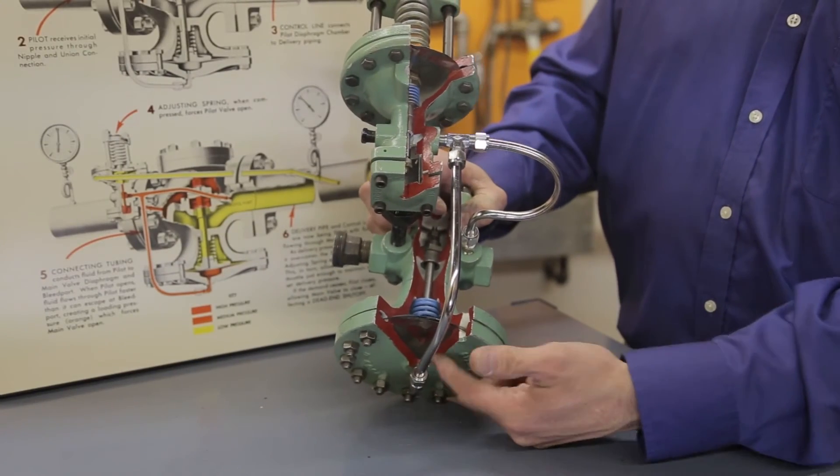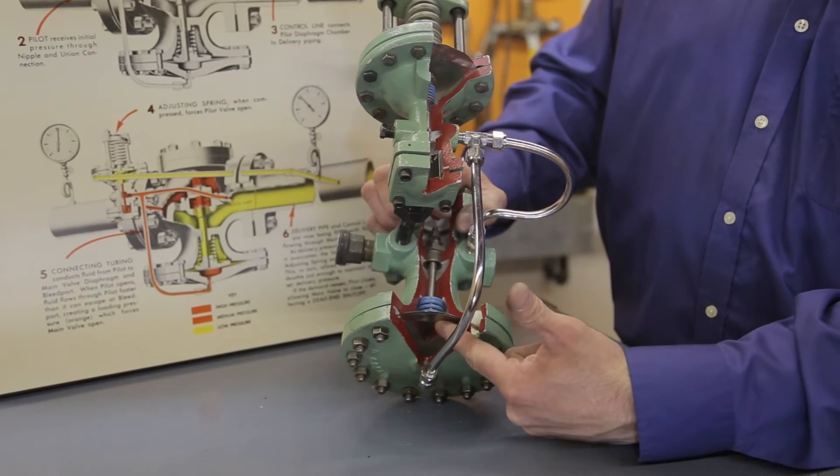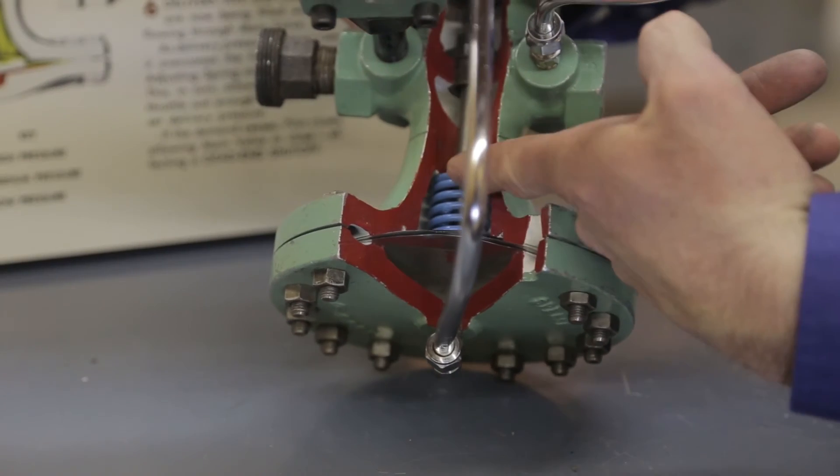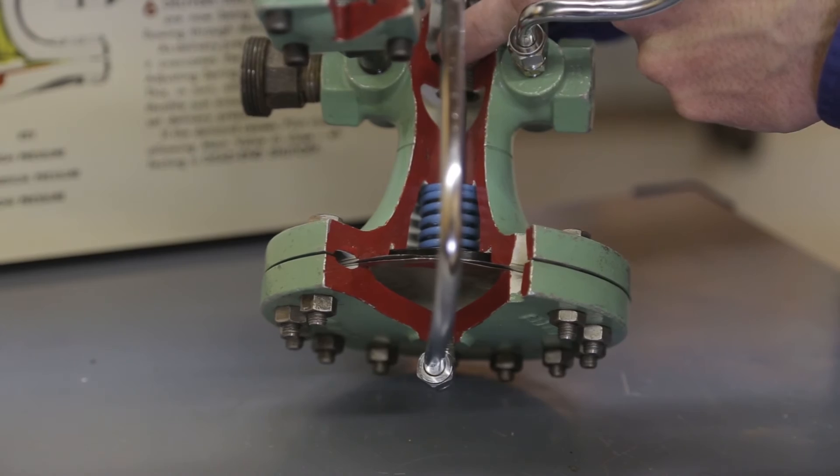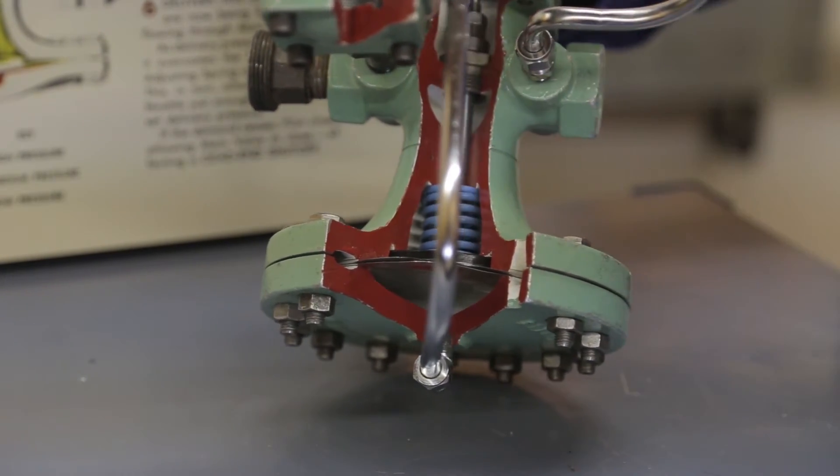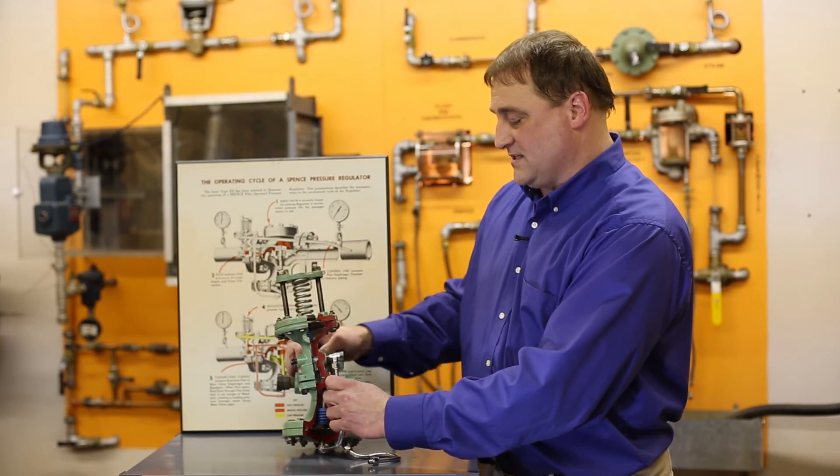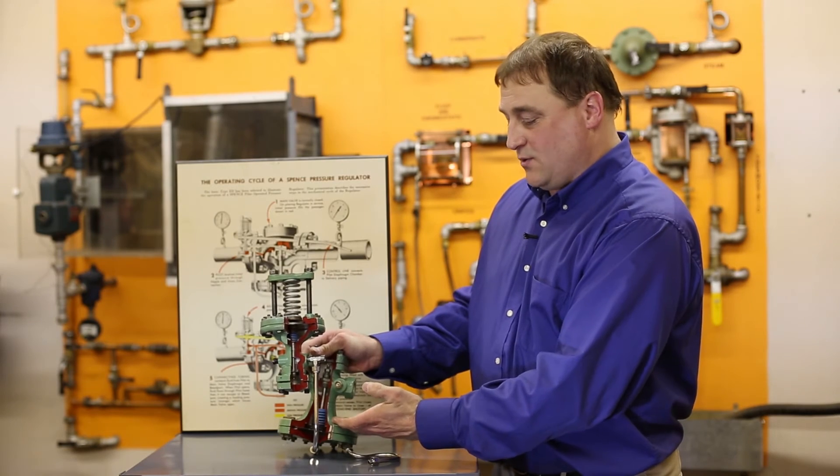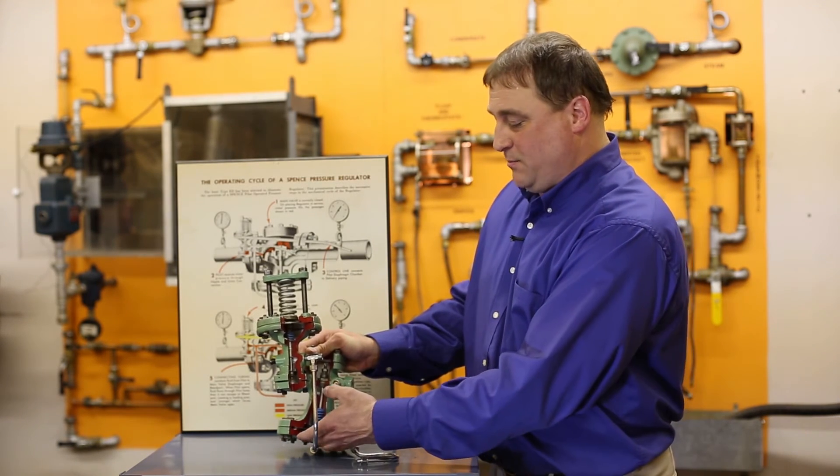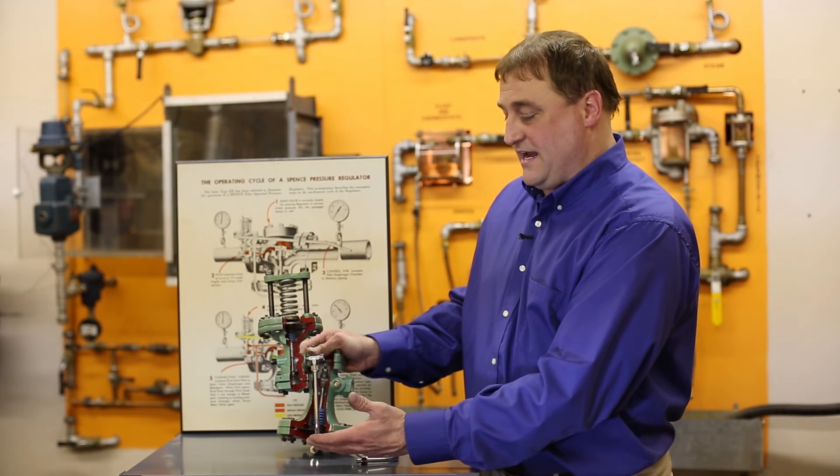Then we have what's called a restriction elbow here. You'll be able to read that we have a restriction port down here. That throttles and controls the amount of fluids that actually stroke the diaphragm. The main valve itself is a fail-closed valve, so we actually have to have a force here to push open this valve through the diaphragm.